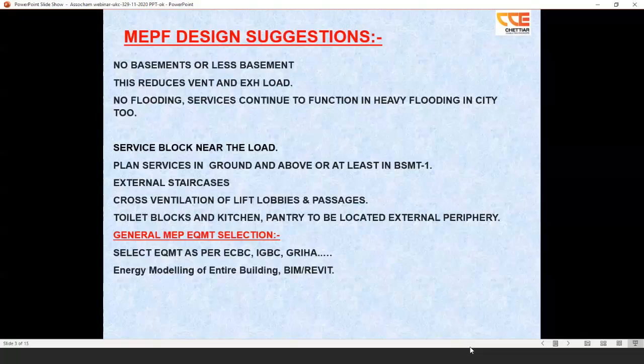So there are certain advices we always give, and this is a challenge posed to many buildings. Look at the external staircases. The moment you put the staircases as part of the internal core, it's very difficult. You are increasing the number of pressurization fans, and the staircase has to depend on mechanical ventilation fans, and the lobbies which are somewhere in the middle of the core, which will make you go for only a pressurized system. So you are dependent on mechanical ventilation, and even for smoke extraction you need fans for all those things, which increases the power consumption. So you are totally going away from sustainability, and you create more problems for the building, and the power consumption actually increases multifold.